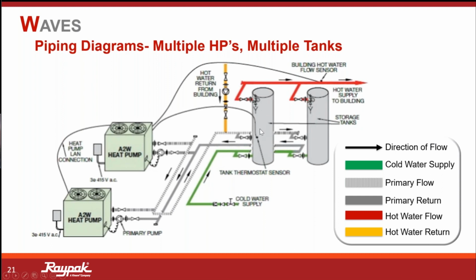But once this draws down in temperature, here's my sensor going into my lead unit. We'll talk about wiring and sensors here in a little bit. So when I actuate a unit, as the demand is needed, we'll engage the circulator. We'll draw water out of that tank, pass through the unit, take our hot supply, and then right back into storage. Again, we're circulating tank concept in and out of that storage tank to these units, 5 to 8 degrees at a time until we elevate that temperature and satisfy on demand.